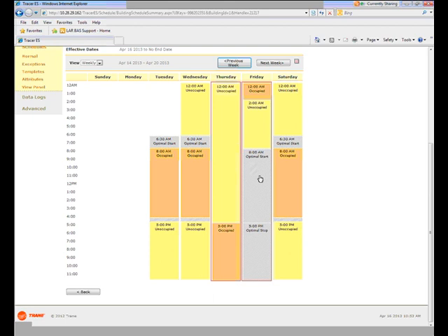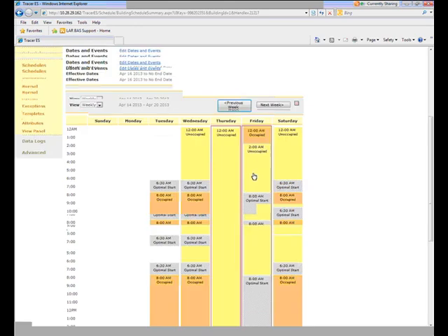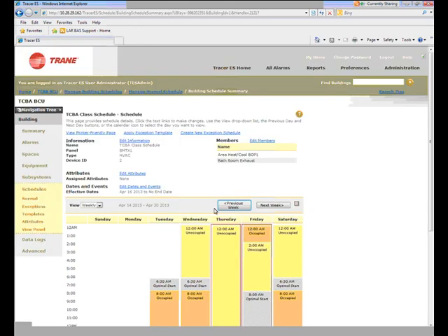Any questions? Would it have been easier to remove the occupied and add a stop? Beg pardon? Would it have been easier to remove, not even add, a stop time on Thursday? So where Thursday all you have is a 5 p.m. occupied and it runs, and then you put an unoccupied on Friday? Yeah, typically if it's on BACnet systems, it's going to go on occupy at midnight unless you put in a default that keeps it occupied.